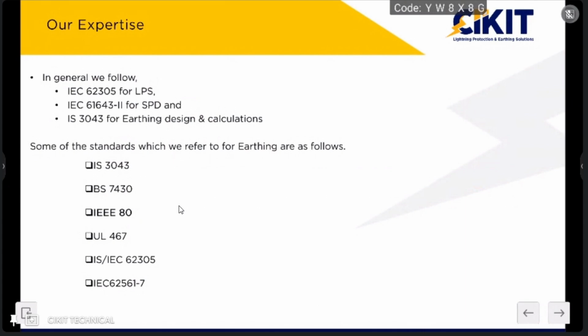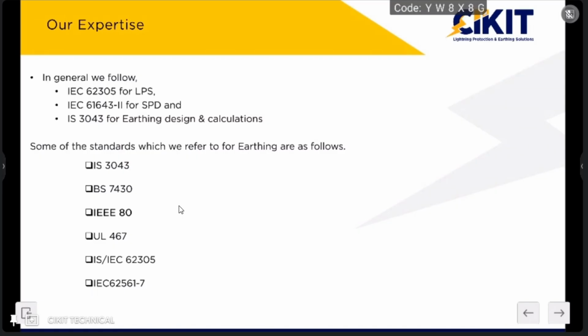As I mentioned, these are some of the standards which we refer related to earthing. So the IS 3043 is the code of practice of earthing which we follow for designing the earth pits for all the kind of applications. BS 7430 is the British standard. IEEE 80 is the standard which we use for designing this earthing for substations. And UL 467 explains about this requirements of earth electrodes, and if you take this copper bonded rods and STGA rods, they have clearly explained about what are all the different tests that has to be done and what are the requirements of that copper bonded rods and STGA rods. And the last one is 62305, which explains about this earthing requirements for lightning protection system. 62561 part 7 has explained about requirements of earth enhancing compounds. So these are the different standards which we will follow for designing this earthing.